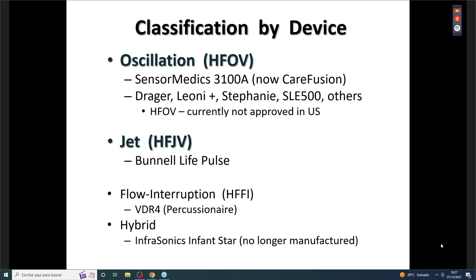Some of the characteristics are shown here for these particular devices. Again, oscillators predominantly have an active expiratory phase versus a passive expiratory phase with the jet. And this leads to differences in rates that are typically used in the support of babies with these modes. Most of the oscillators use a fixed I:E ratio. Currently, the most common ratio in the 3100A is 1:2, whereas with the Draeger, there are investigations where people use both a 1:1 and a 1:2 approach.